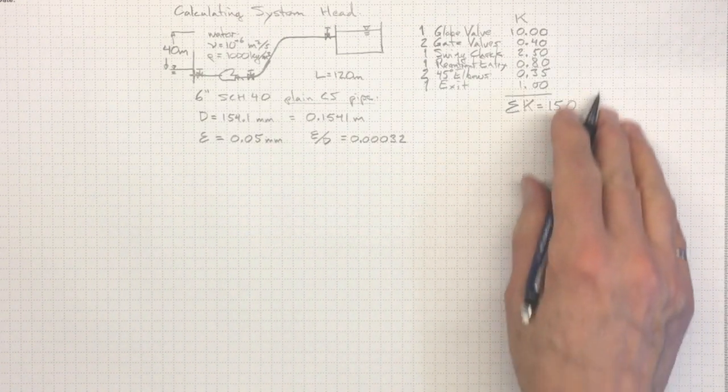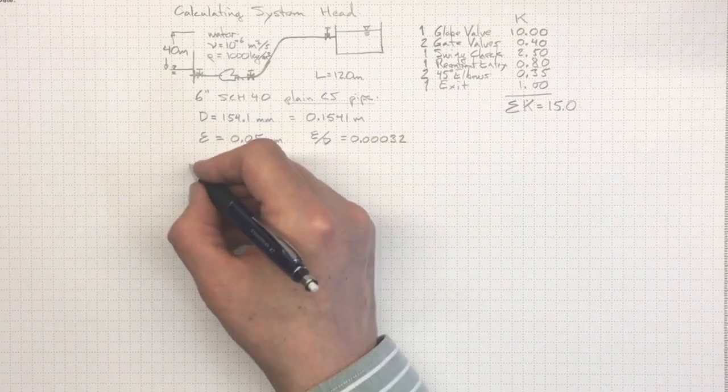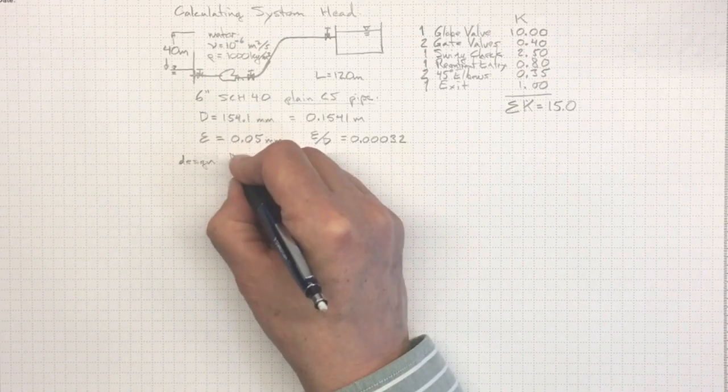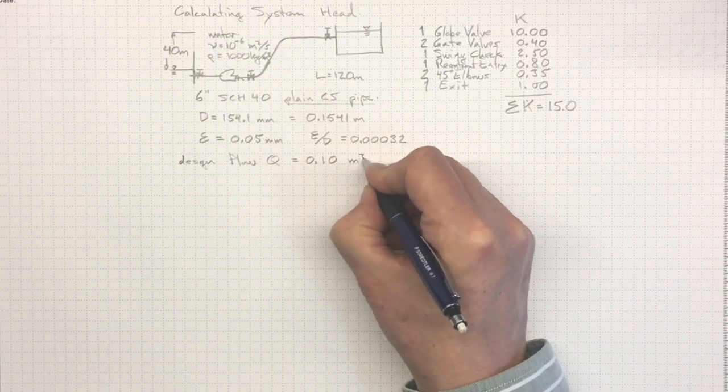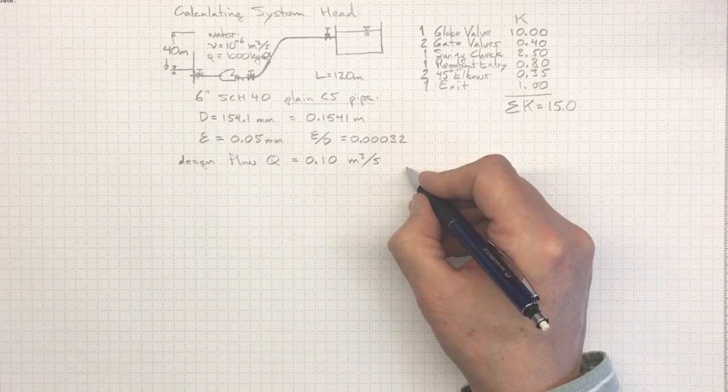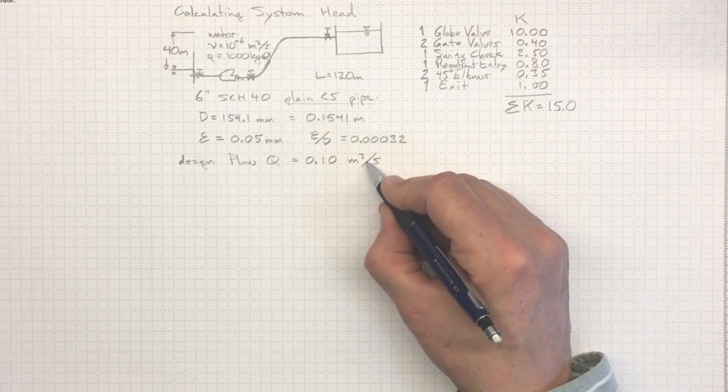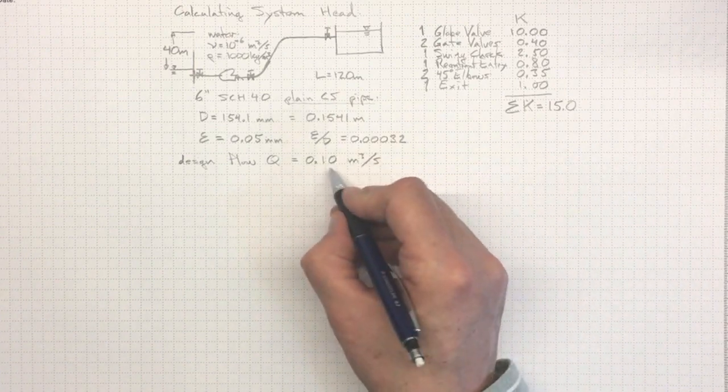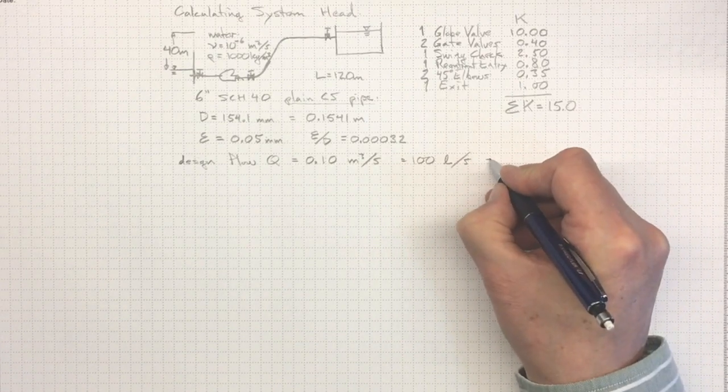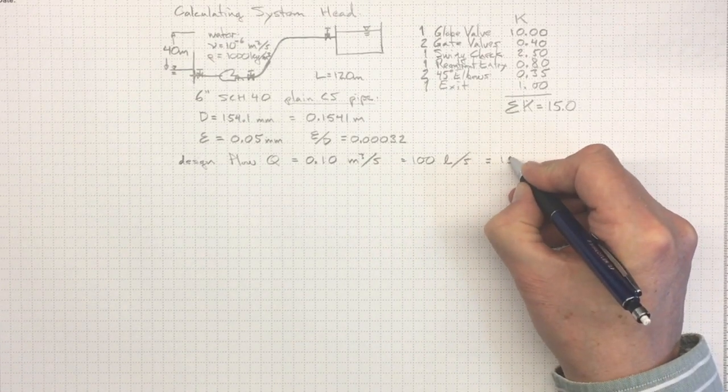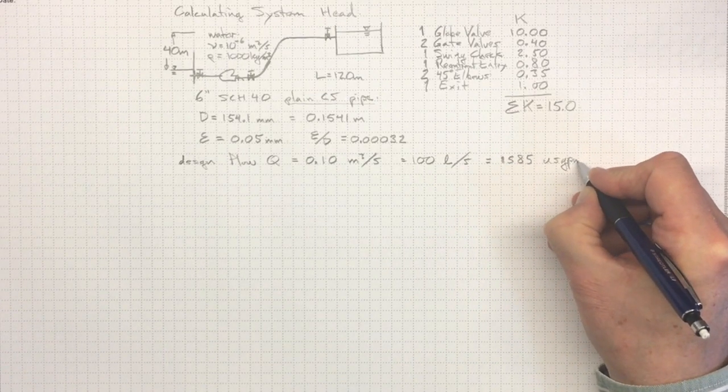Now, we've got a piping system here. And I picked that 6-inch pipe as probably being okay to meet my design flow rate of about 0.1 cubic meters per second. Now, 0.1 cubic meters per second may seem like a small number. It's a fraction of a cubic meter per second. But that's actually quite a large flow of water. 0.1 cubic meters, that's 100 liters every second. Or, in units that you'll see fairly commonly, 1,585 U.S. gallons per minute.